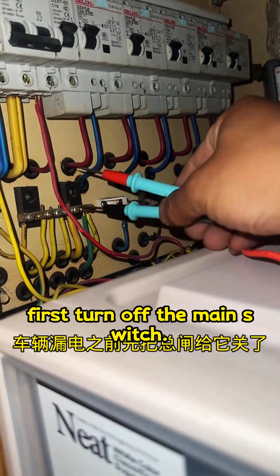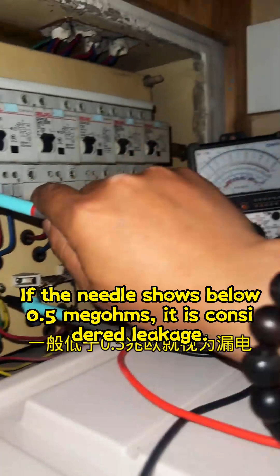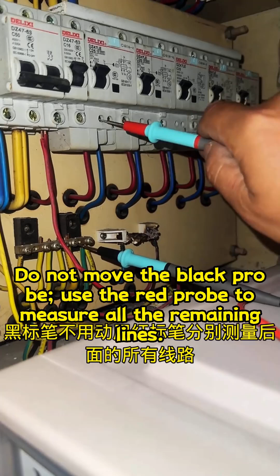Before measuring for leakage, first turn off the main switch. Place the black probe on the ground bar. Then, use the red probe to measure all branch lines one by one. If the needle shows below 0.5 megohms, it is considered leakage. Do not move the black probe. Use the red probe to measure all the remaining lines.